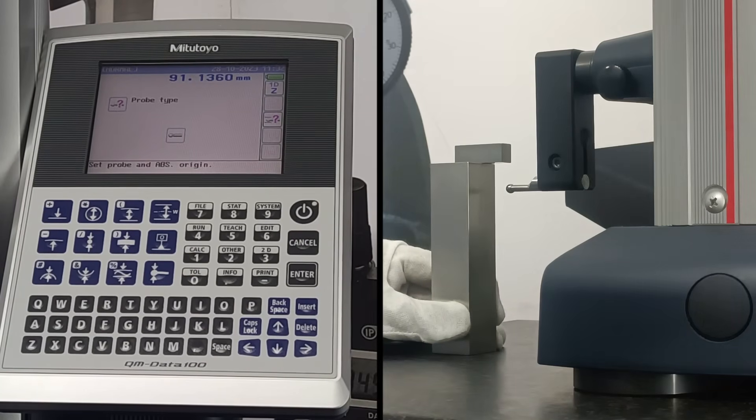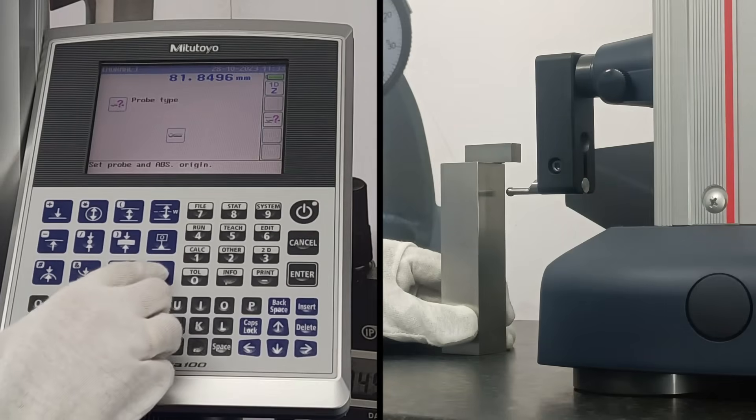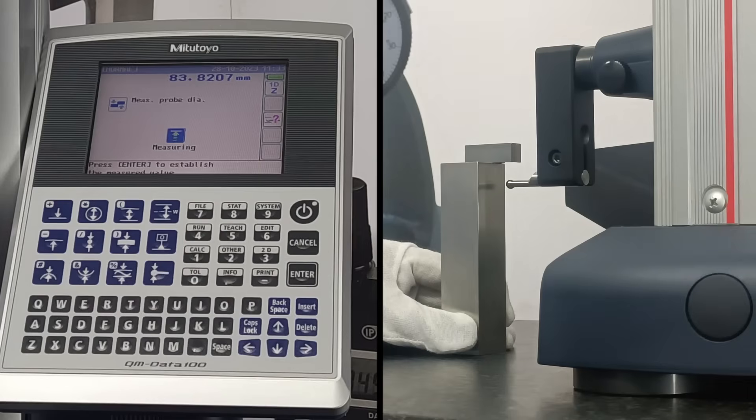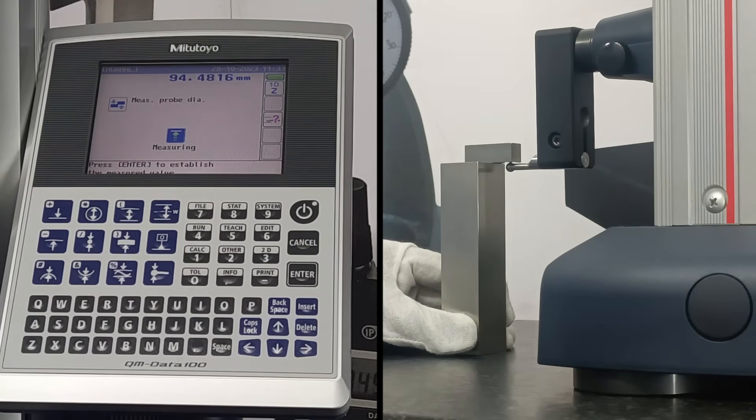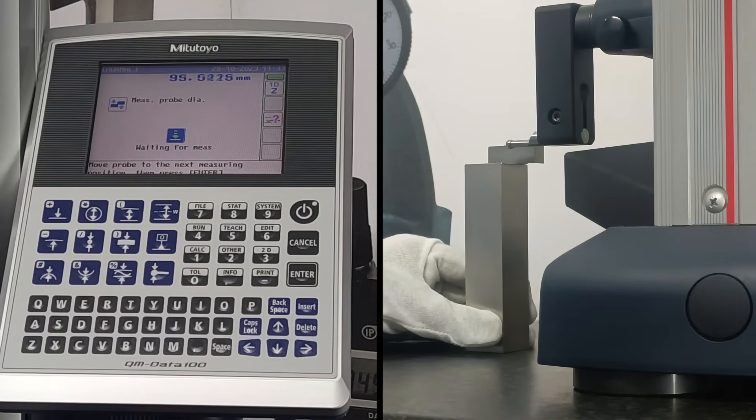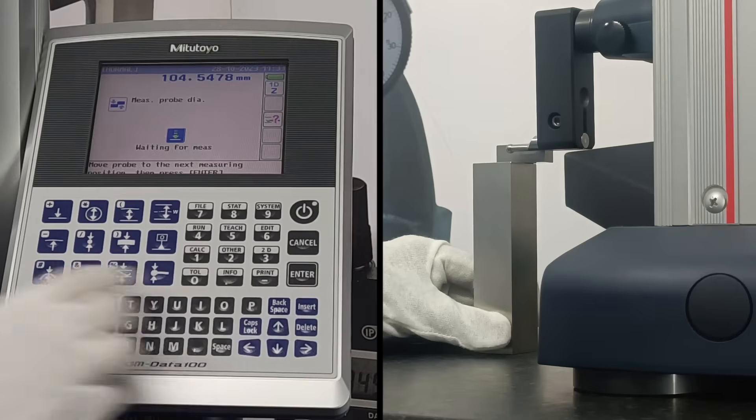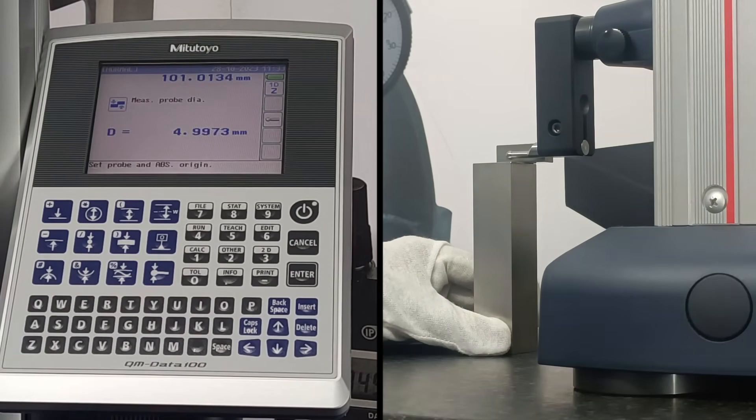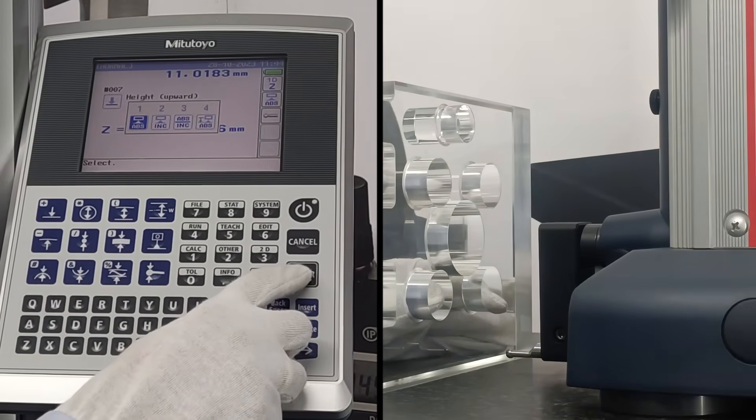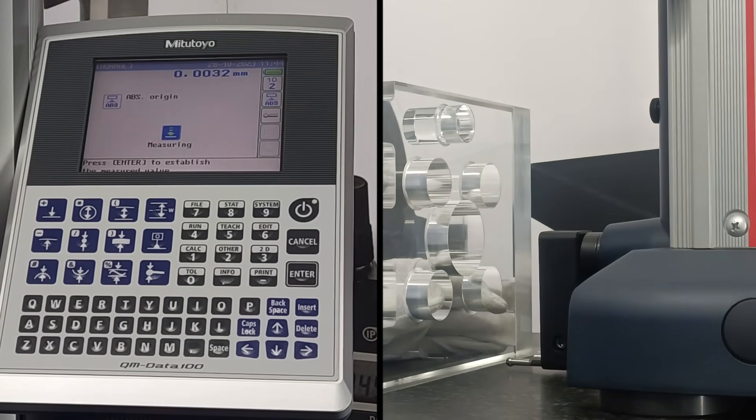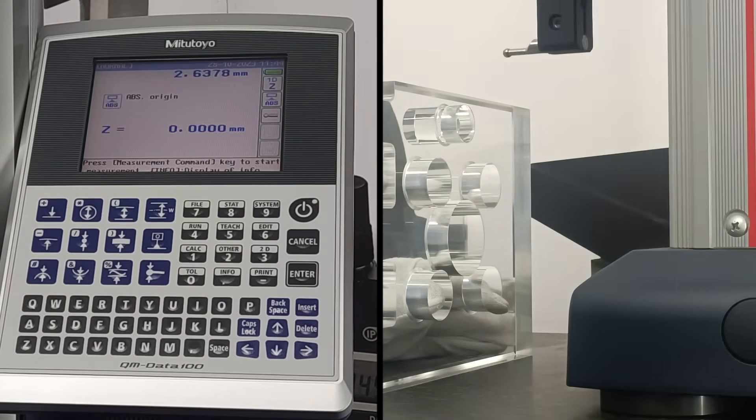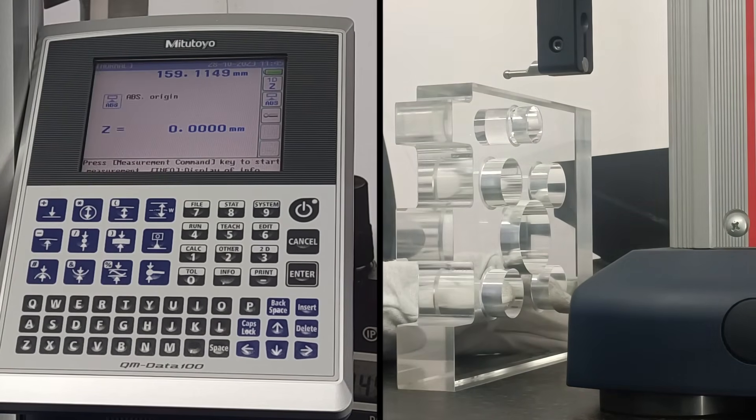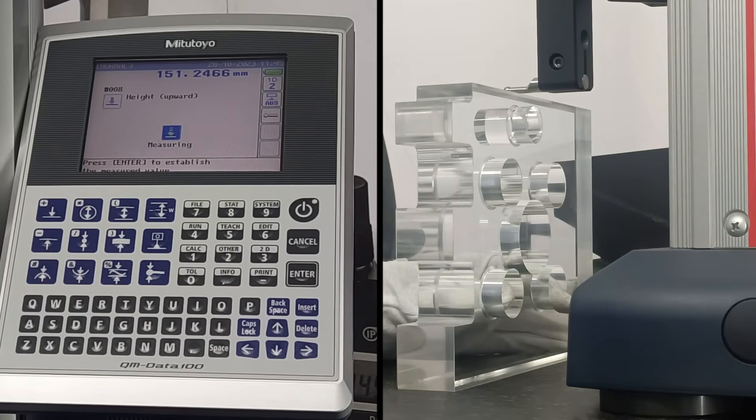Let's set the probe diameter. Press probe key and select second option. Measure upward and downward positions. Wait until the buzzer sounds. Now our probe diameter is calculated. Let's see the various measurement options in detail. Set absolute origin before measurement. Press downward arrow to measure height.